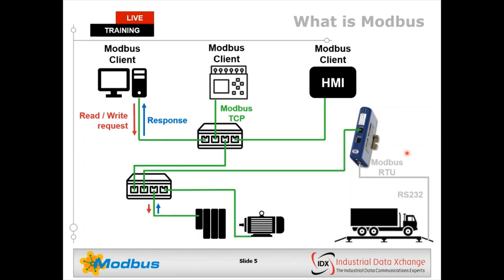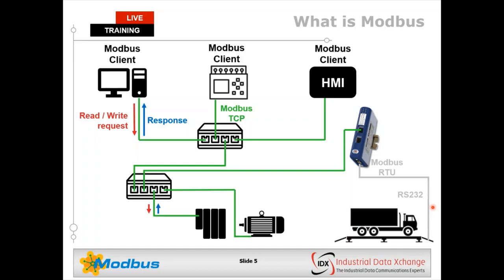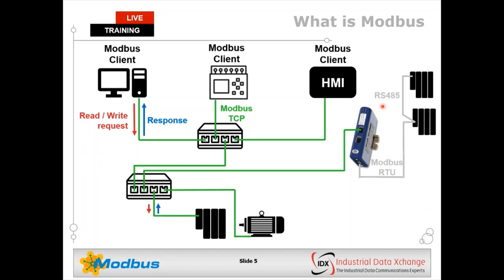There are two main Modbus RTU standards. RS-232 is point-to-point, meaning you only have two devices on the network — your Modbus master and your Modbus slave device. This gateway acts as a Modbus RTU master on the serial side but also as a Modbus TCP slave to feed information to Modbus TCP devices, and it can do both RS-232 and RS-485. With RS-485, you can have a whole host of devices that daisy-chain together and share the same medium.